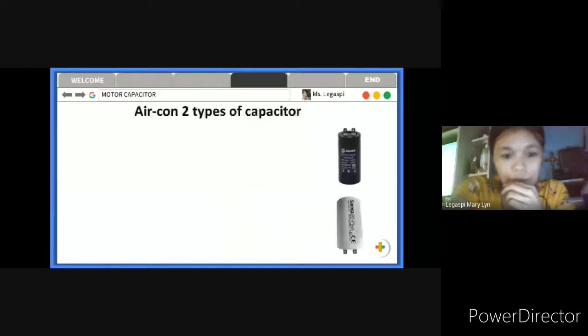So when we say starting capacitor, it is found in the circuit of start windings when the motor is starting. This capacitor contains higher capacitance than a run capacitor. It varies, but start capacitor will measure between 70 and 120 microfarad. So starting capacitor is responsible for starting the aircon, especially kapag malaki yung microfarad niya, di ba sinabi yun ni Sir last time? Also, start capacitor provides an immediate electrical push to get the motor rotation started. Note lang dito na without a start capacitor, when the voltage is applied, the motor would just hum or sound like a bee. That's why the starting capacitor is very important.